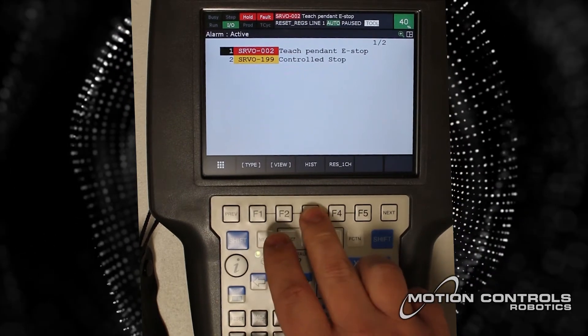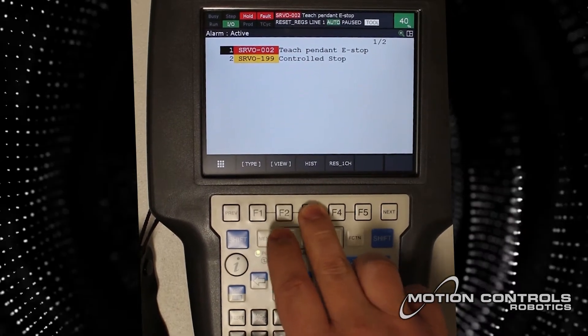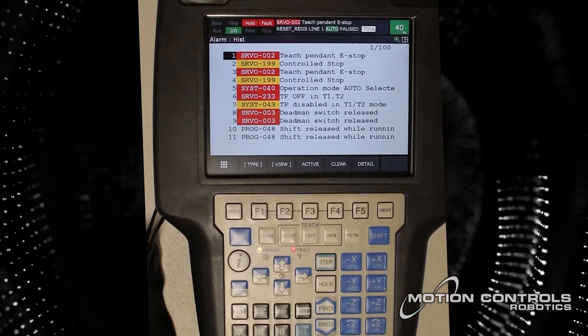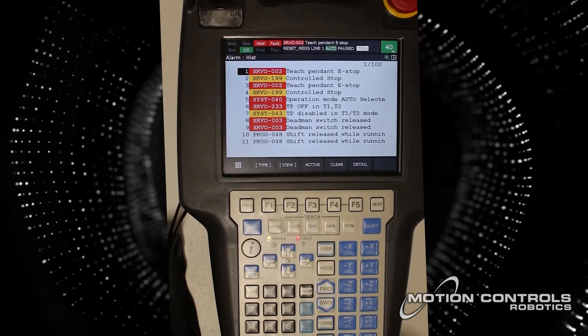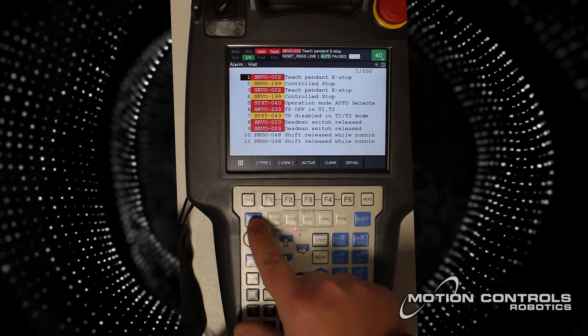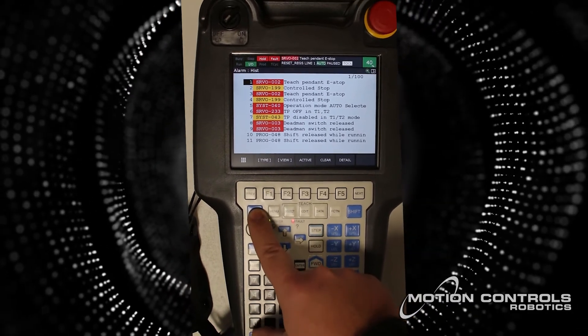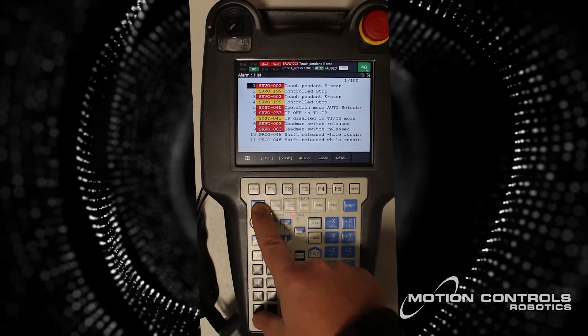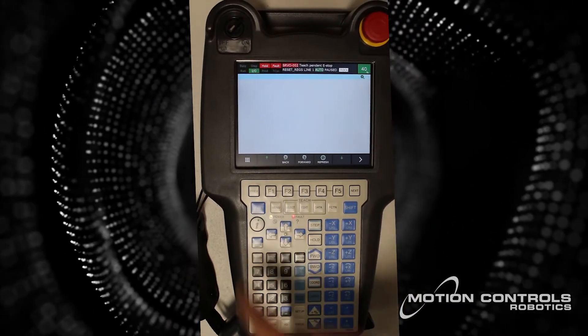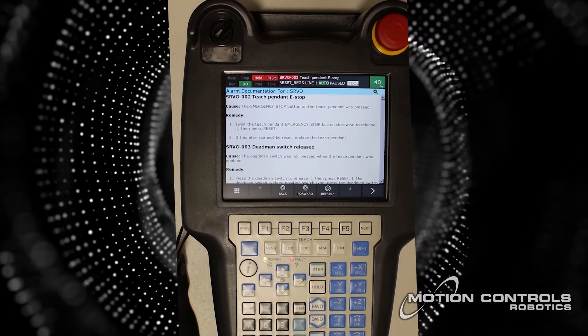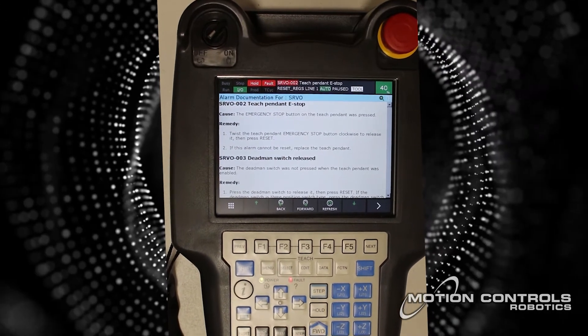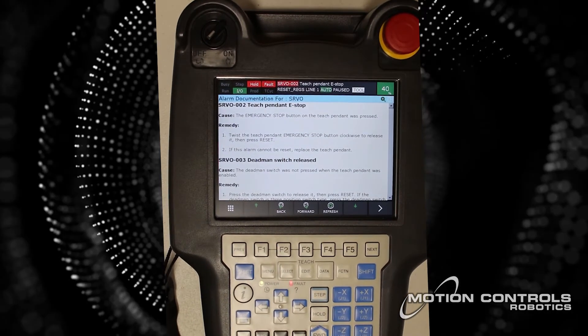Now go to F3 History. This area contains the last 100 alarms or faults that have occurred. By pressing the Shift and Diagnosis Help button together, you will go to a Troubleshooting area where there are alarm causes and remedies.